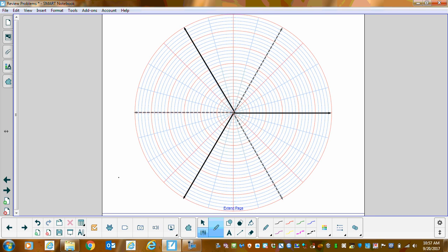Now, what do we know about a delta as far as phase voltage and line voltage are concerned? They're the same, right? So we can make the statement then that voltage line equals voltage phase in a delta. Now, the currents, of course, in an unbalanced delta, can we use the statement that our line current is equal to √3 times the phase in an unbalanced delta? No. Can we in a balanced delta? Yes. Seeing as how we do not have a balanced delta here, we have to look at each individual phase.